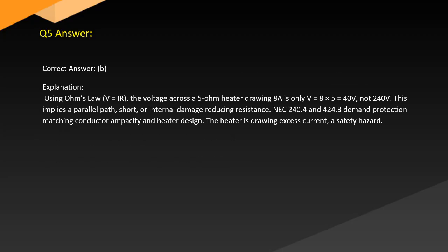Answer. Correct answer: B. Explanation. Using Ohm's law, V equals I times R. The voltage across a 5 ohm heater drawing 8 amps is only V equals 8 × 5 equals 40 volts, not 240 volts. This implies a parallel path, short, or internal damage reducing resistance. NEC 240.4 and 424.3 demand protection matching conductor ampacity and heater design. The heater is drawing excess current.